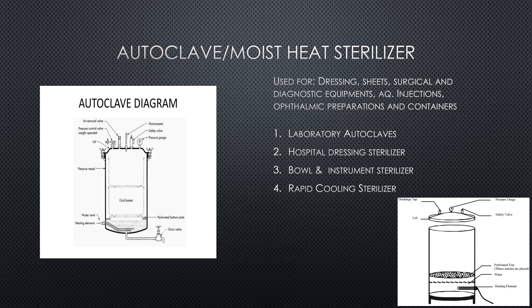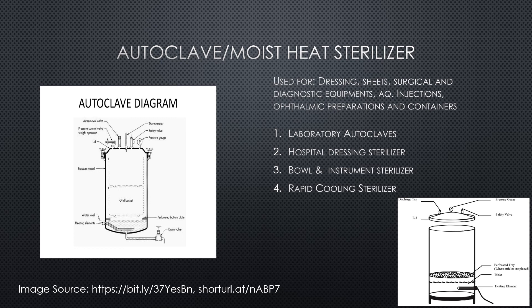Industrial and hospital sterilizers are usually supplied with dry saturated steam, with attention paid to removing water droplets to prevent water fog in the sterilizer. The portable autoclave is a stainless steel vessel designed to withstand steam pressure, with an electric heater to produce steam, used for small pilot or laboratory scale sterilization and for treatment of instruments and utensils. Large scale sterilizers will be covered in the next video.